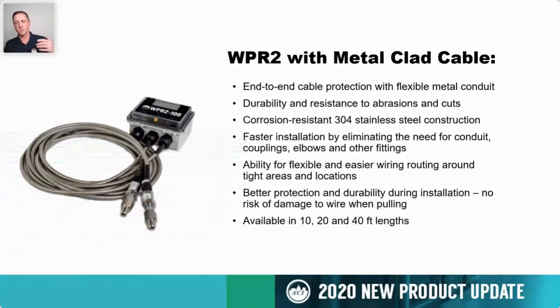This can be run through exposed space without having to run additional piping or additional conduit. It makes for a much greater level of protection and durability during installation, because if this cable is pulled on while it's being installed or while it's in operation, if somebody catches the cable with a ladder or hooks onto it somehow, it's just the metal cladding that is pulled. It's not the internal cable. And so this is a very durable, rugged addition to our wet-to-wet differential pressure transducer to provide a higher level of protection both during install and also during continued operation. The standard lengths are 10, 20, and 40 feet, and we do have other lengths available by special order.